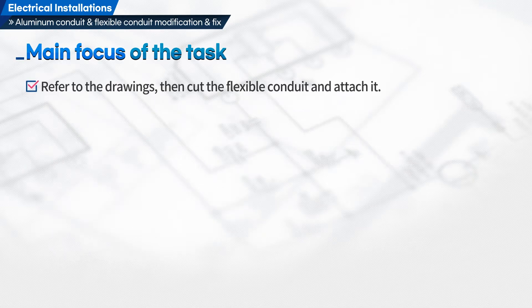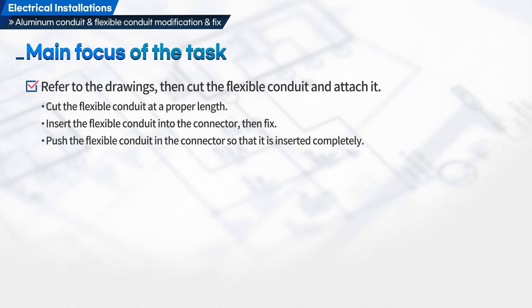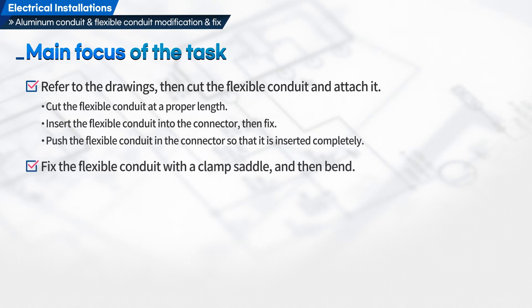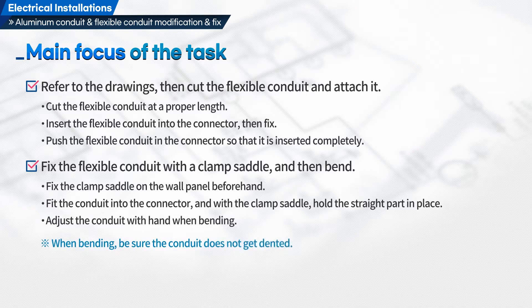Fifth, refer to the drawings, then cut the flexible conduit and attach it. Cut the flexible conduit to a proper length. Insert the flexible conduit into the connector, then fix it. Push the flexible conduit into the connector so that it is inserted completely. Sixth, fix the flexible conduit with a clamp saddle and then bend. Fix the clamp saddle on the wall panel beforehand. Fit the conduit into the connector and with the clamp saddle, hold the straight part in place. Adjust the conduit by hand when bending, making sure the conduit does not get dented.